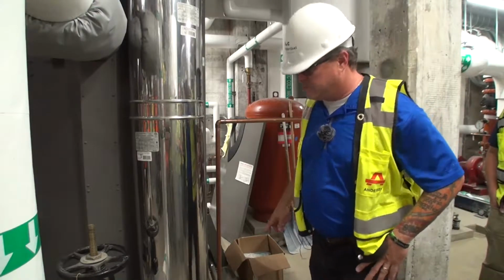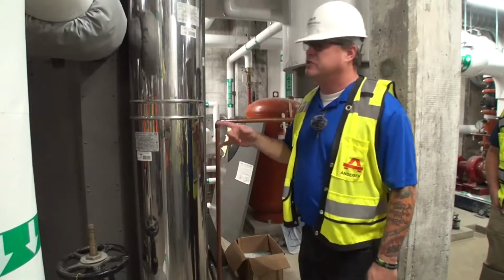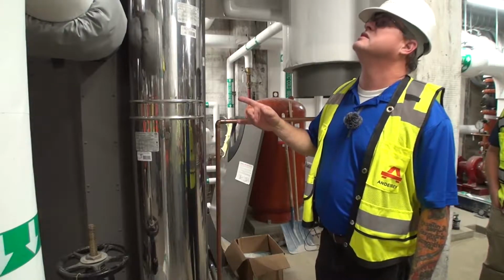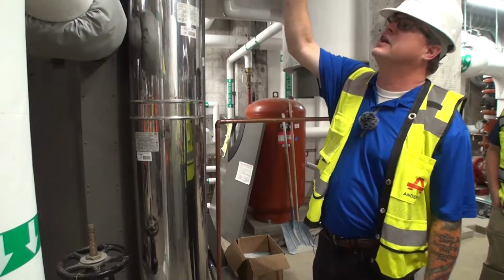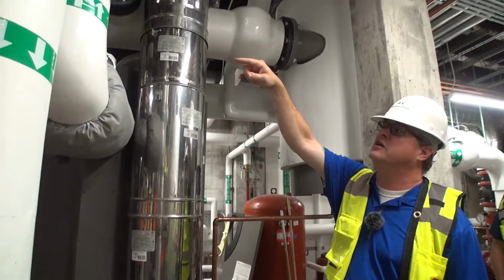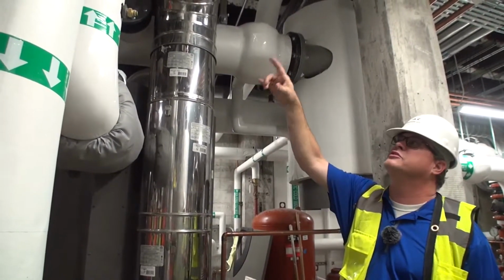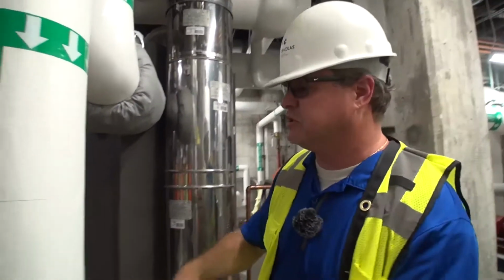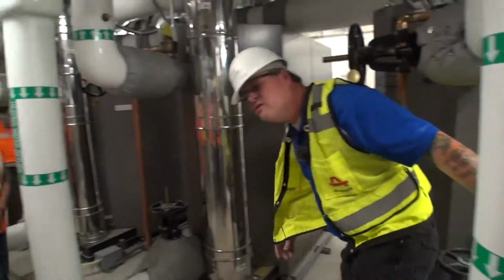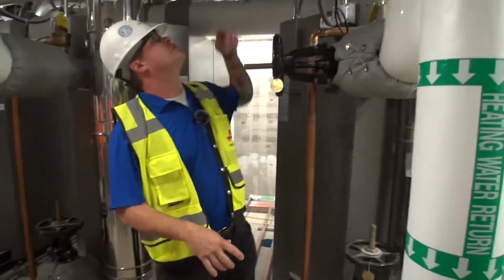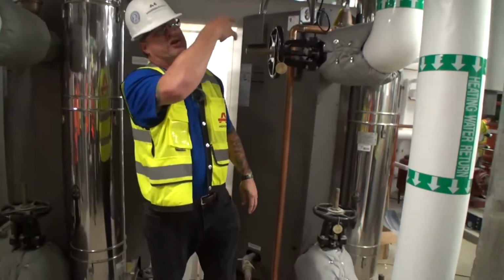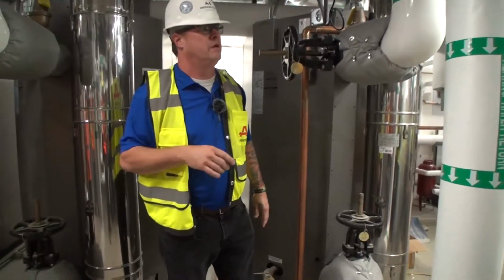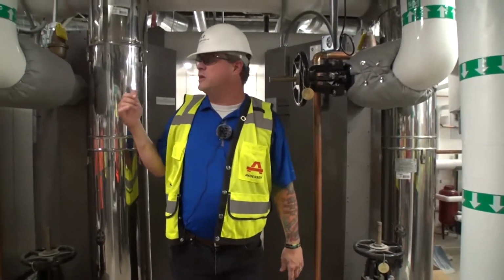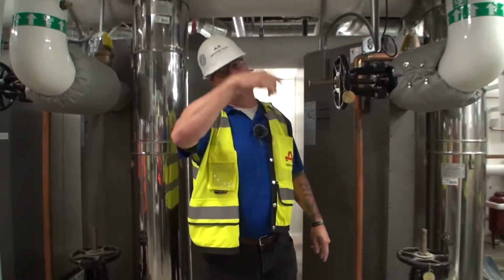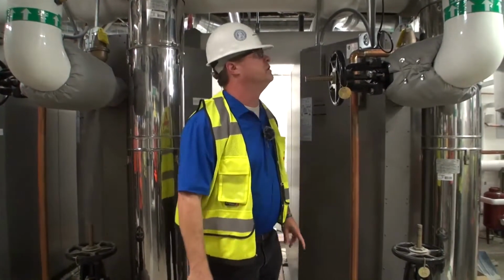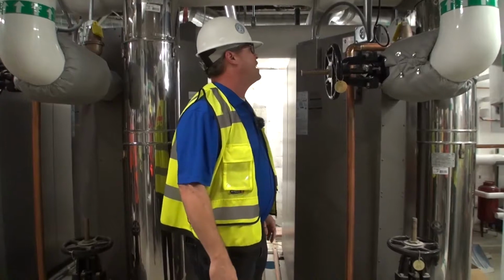Other than that, how are these controlled? I don't see any isolation. Oh, okay, so valves. You are shutting off valves on the boilers coming on, so these valves. And then there's a position switch on these valves that shows open, closed, and so on. The one that's open should be the fired boiler. The other one should be closed, because you don't want to flow through the boiler on an off boiler. It's just good practice.